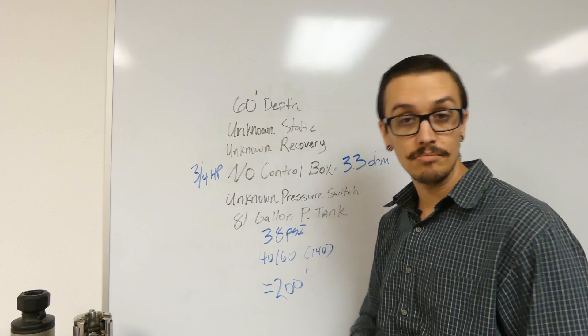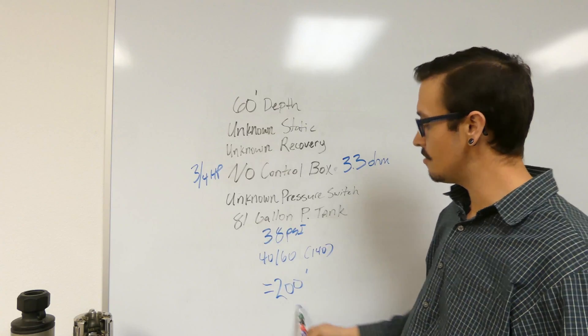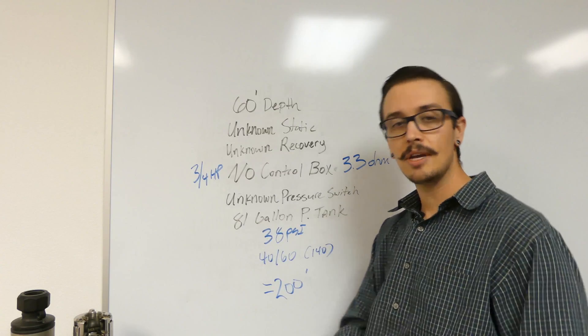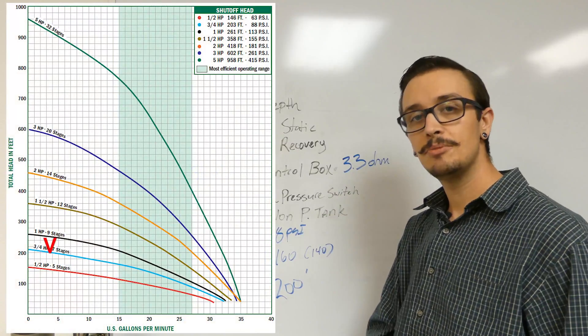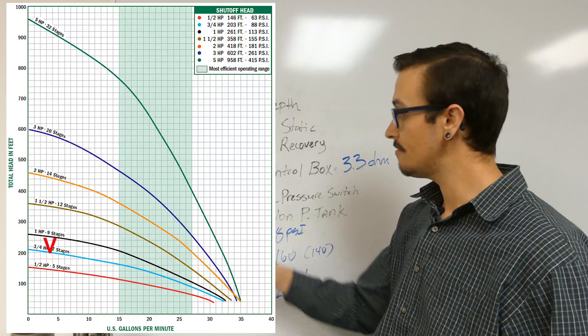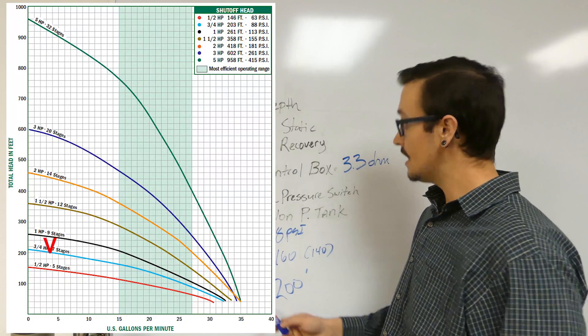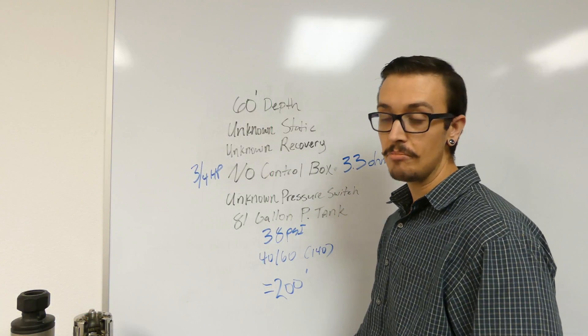Or maybe not. So anyways, let's work this out just a little bit farther. We know 200 feet, three-quarter horsepower. We're looking at the 20 gallon minute pump curve. You can see on this pump curve it is a dead miss if our static, if we actually need to pump at the pump level which is 60 feet deep. This pump is a dead miss if we're trying to get up to 60 PSI.